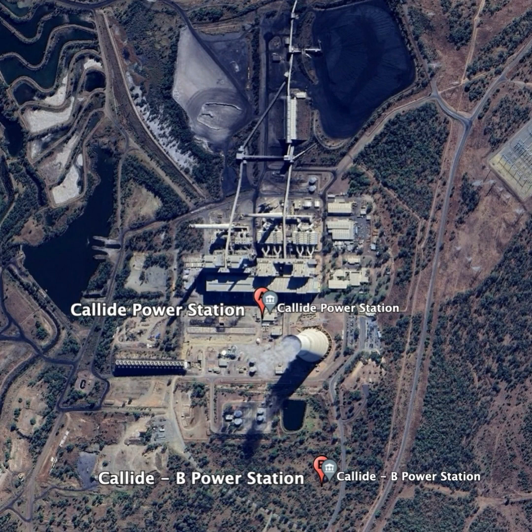At 2:06 p.m., the generator, or rather now a motor, and its connected turbine blades were now flexing so much the blades started catching on the turbine housing. The blades quickly eroded the impacted metal turbine housing in 9 separate locations and sent shrapnel at high velocity through the turbine hall as the turbine catastrophically failed. A 2-ton steel shaft segment flew 5 meters from the turbine, and debris was launched 20 meters into the air, punching holes through the roof of the turbine hall.